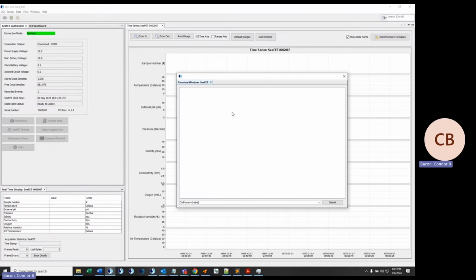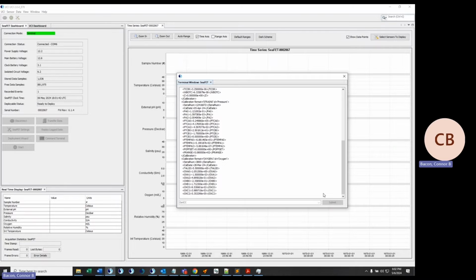The instrument will respond immediately to all commands when not sampling. For instance, getCC will display your system's calibration coefficients, and DS will show your instrument's information and status. Some commands are not shown in the drop-down menu and can be found in the Deep SeapHOx V2 manual and the latest version of the 37 SMP ODO manual. For any command meant specifically for the 37 SMP ODO, you will need to add the prefix send37=. The terminal is not required for every deployment, but can be helpful for changing settings without using the deployment wizard or for troubleshooting.